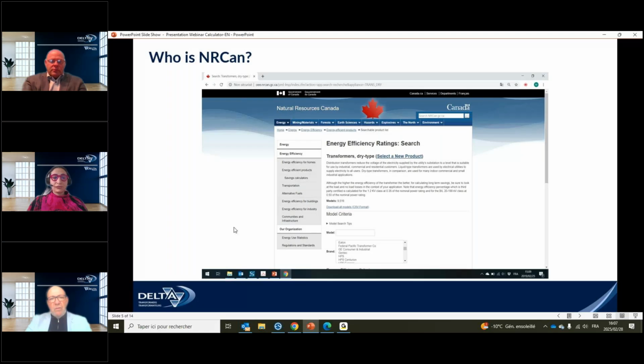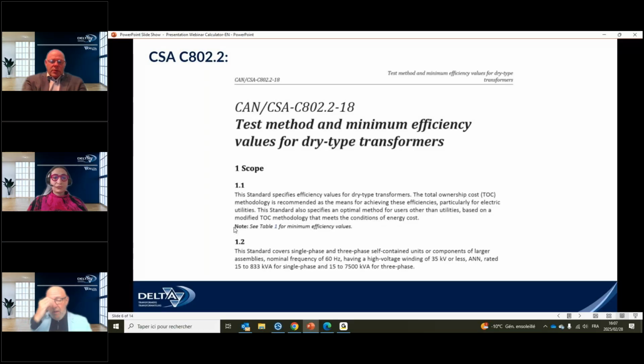So that's for the portion of NRCan, and then we have the standard from CSA, which is C802.2. That's the standard, which is mainly the test method and the values of efficiency that we have to meet for transformers. So NRCan dictates the law, and we use the CSA standard to conduct the test and to ensure that we meet those levels dictated in that standard.